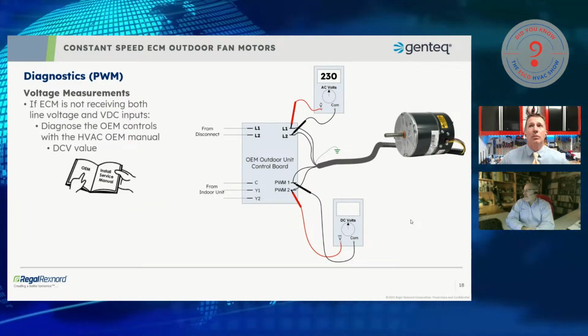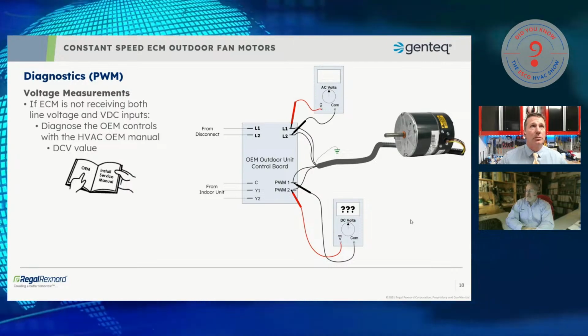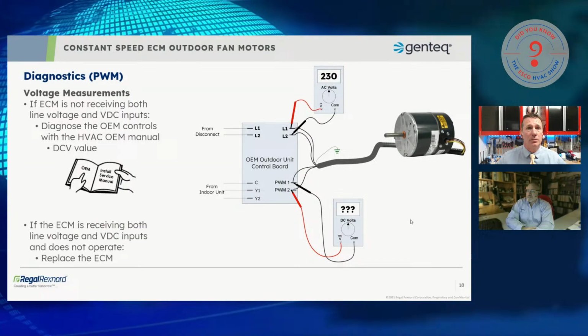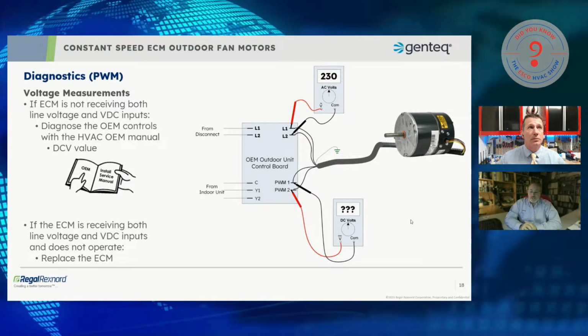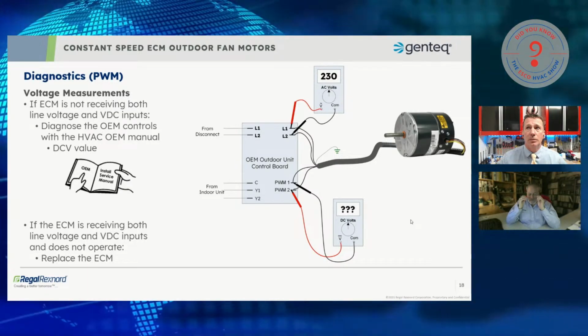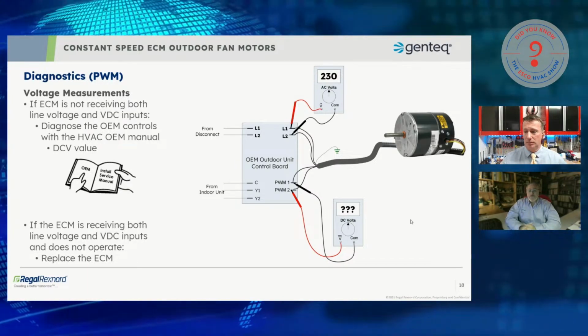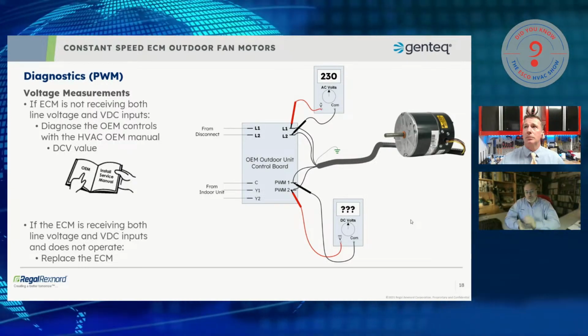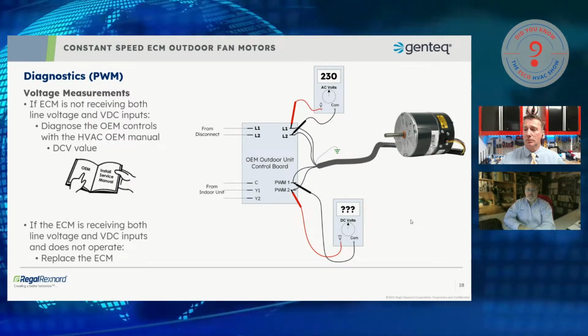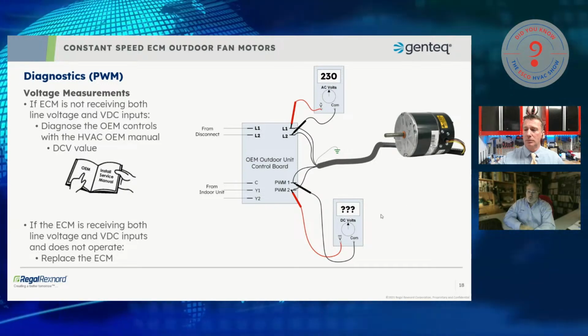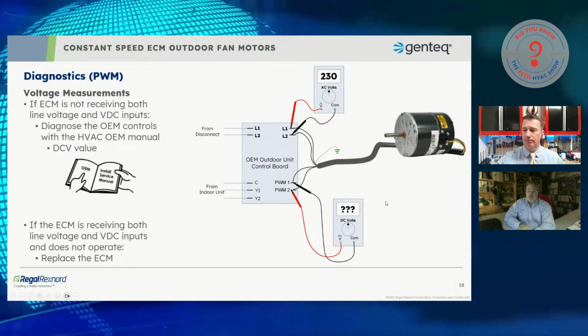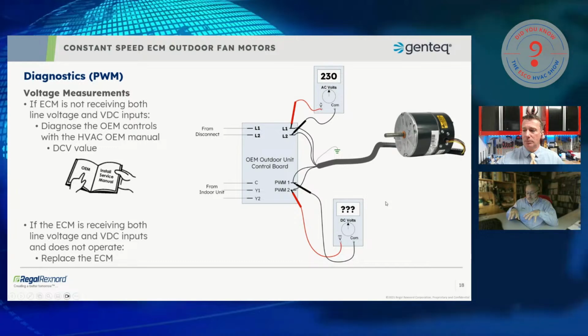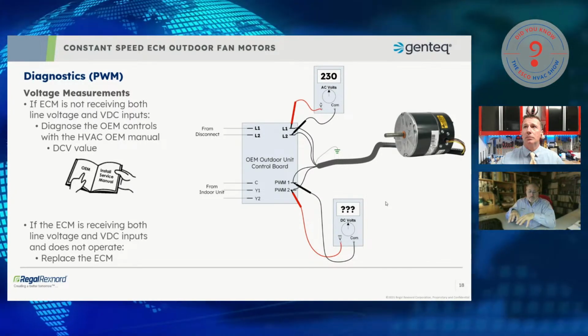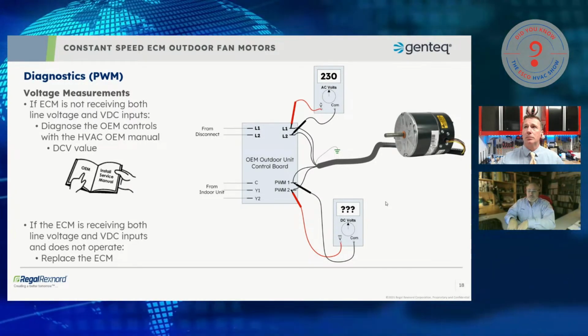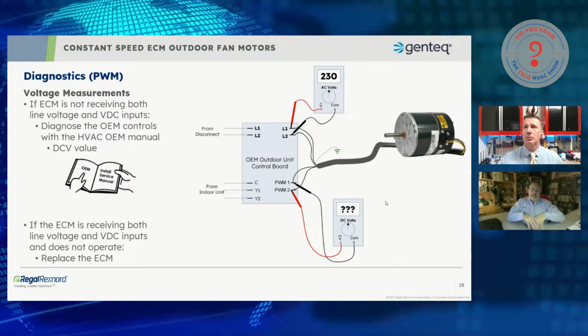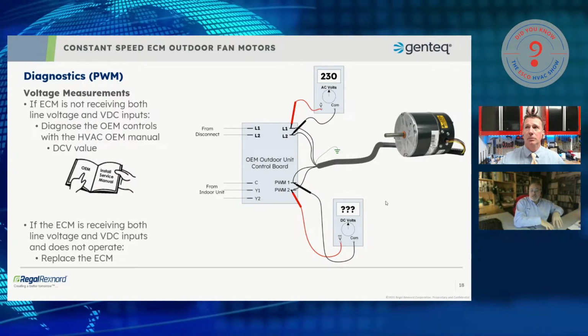You betcha. So again, we talked about the AC and the DC volts. Must have both. And for the DC voltage, we will need to get that from the manufacturer. And the first one you measure, don't write those numbers down and assume those are going to be the same DC voltage from one OEM to another, or even from one OEM system to another. So, for example, if I'm working on, I'll just use a manufacturer's name, if I'm working on a Trane split system, 16 plus SEER, and I measure the DC voltages, and I go to a Trane package unit, those DC voltages could be different.